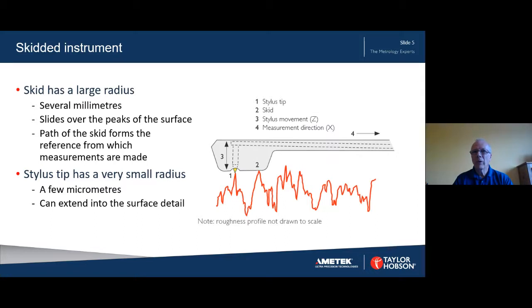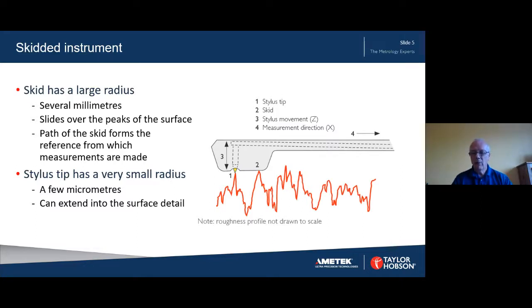Looking at the instrument in this diagram we can see how the skid will move over the peaks of the surface. The profile depths will be measured by the stylus measuring from whatever height the skid rests at. An important principle can be seen if we consider measurement of a valley near the current location and in a location to the extreme right of the profile. It's clear that the skid will be at different heights in the two locations. The skidded instrument would therefore measure a smaller valley depth on the right hand side than a skidless instrument would. In practice, because of the radius of the skid being very large compared to the spacing of the peaks, the difference in recorded heights should be very small and within the uncertainty of measurement.